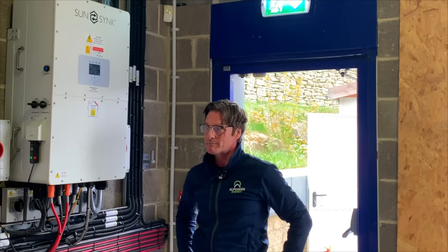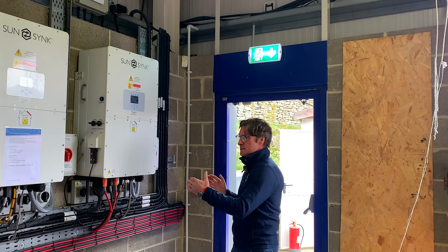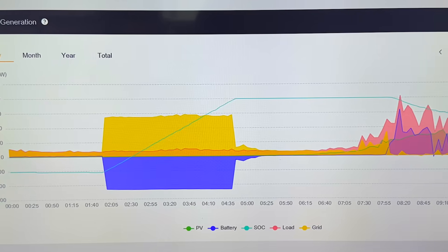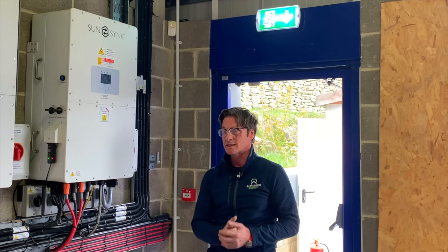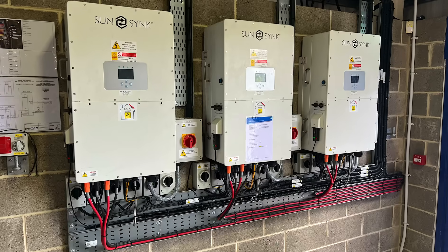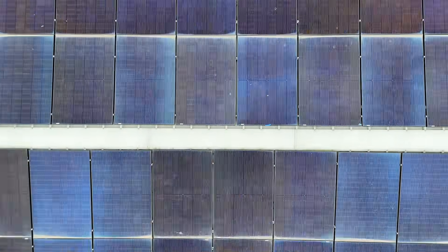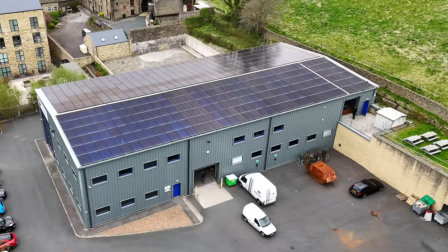Moving the inverters indoors freed up space, which they took advantage of to add additional battery storage. The original install had a 64 kilowatt-hour battery attached to each inverter, but with the Sunsynk system you can cluster up to 10 batteries through one inverter. Looking at Tim's load profile, they suggested adding another three batteries. They now have 384 kilowatt-hours of battery storage split across three inverters — 128 kilowatt-hours on each. Installed on the roof are 432 solar modules delivering a peak generation capacity of 146 kilowatts.